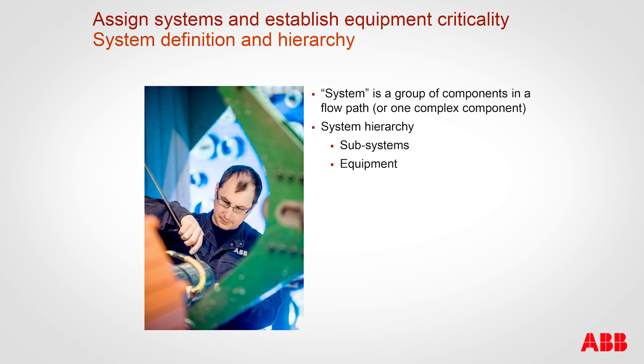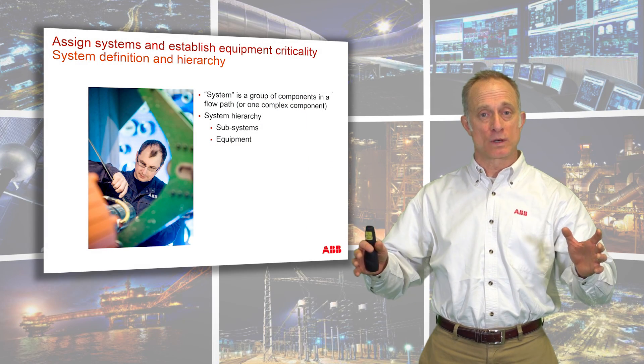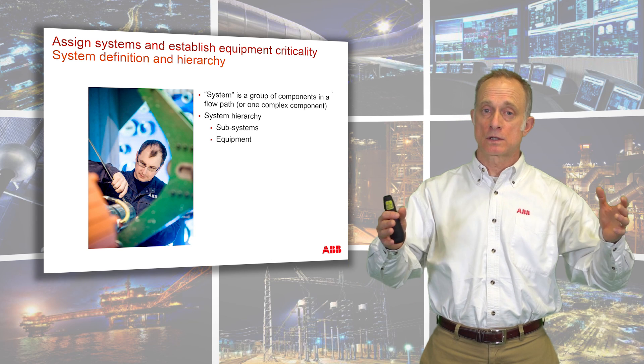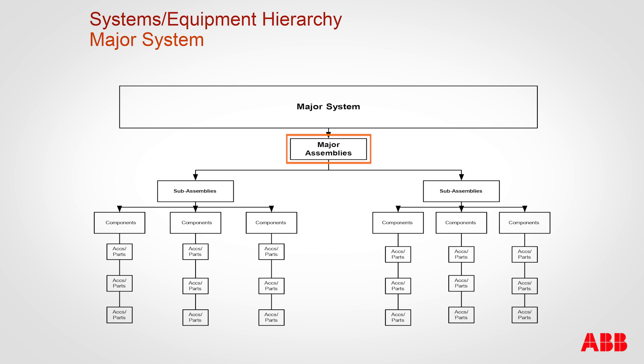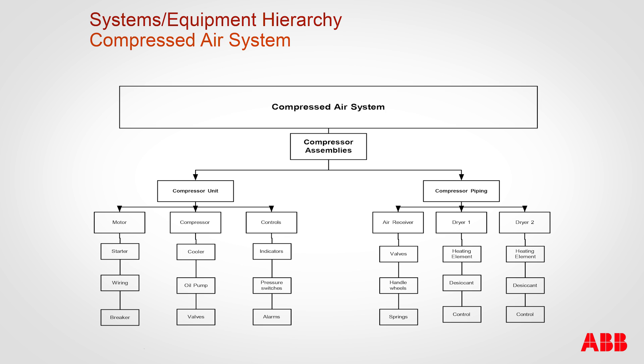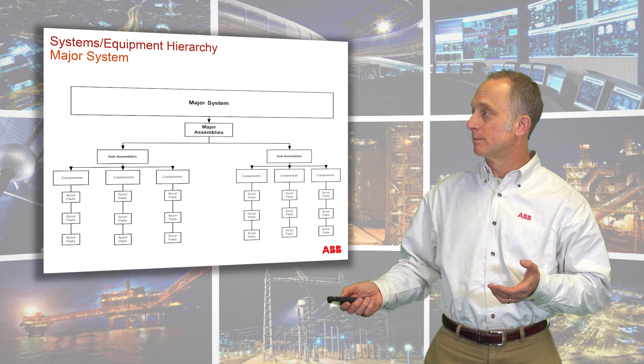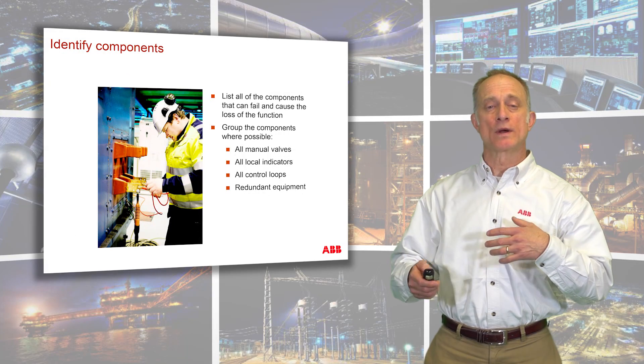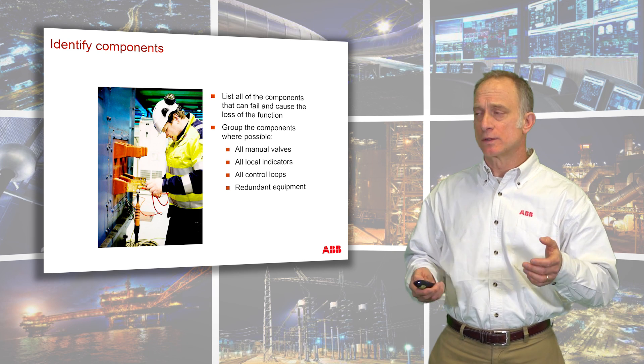Before we can assign criticality, we need to establish the systems. A system is a group of components in an equipment category — a piece of equipment and all its subcomponents, or it could be one singular complex piece of equipment. We'd have a major system with major assemblies, major sub-assemblies, components, and we get down to a part level. For example, a compressed air system would have compressor assemblies, compressor units, and each compressor unit would have a motor, a compressor, and controls — and then you get down to a parts level.